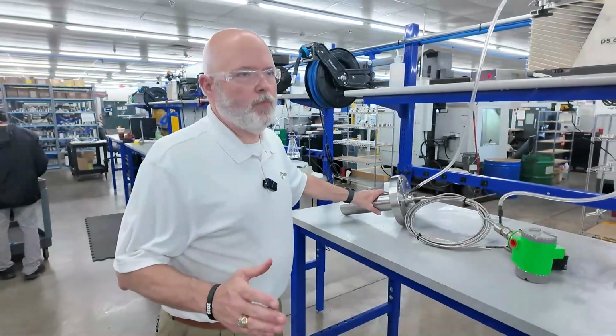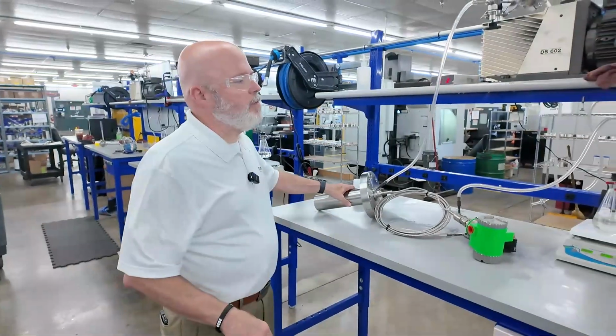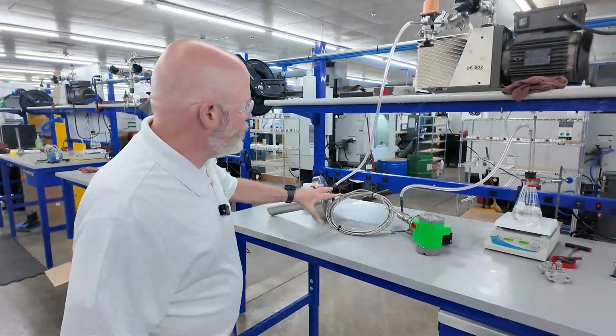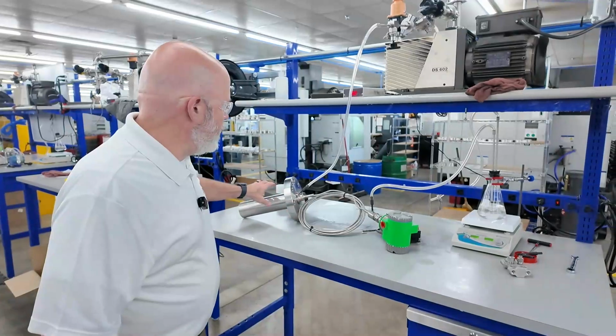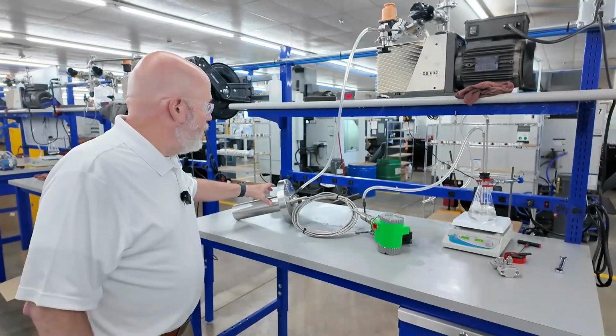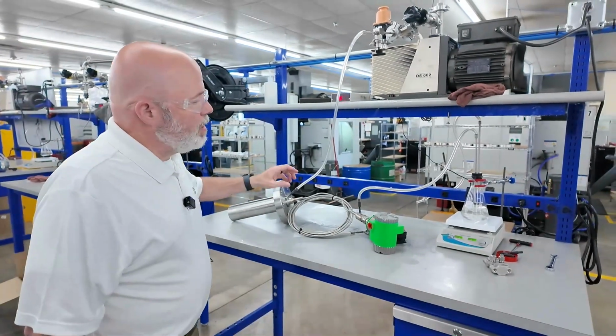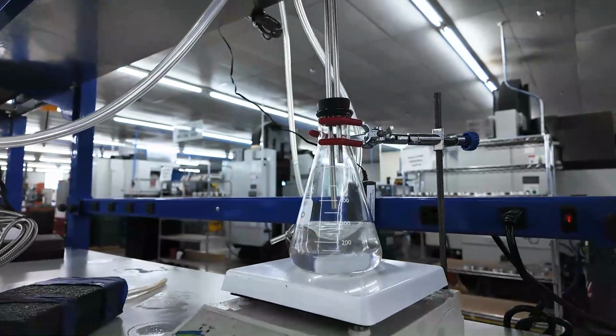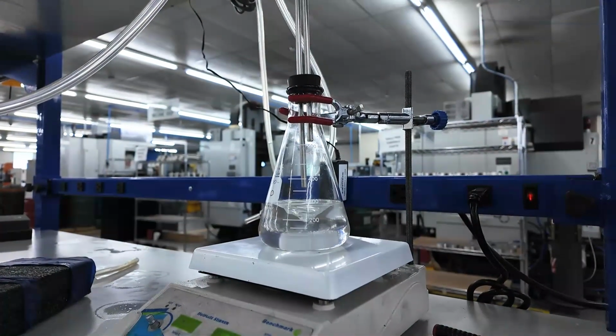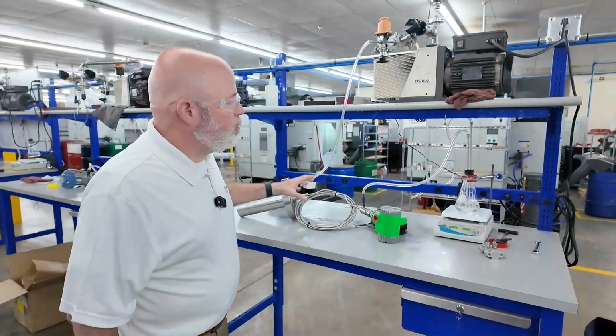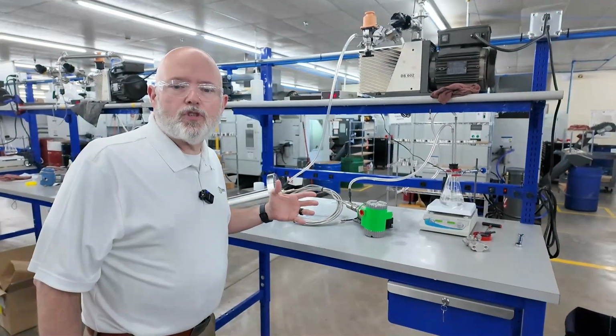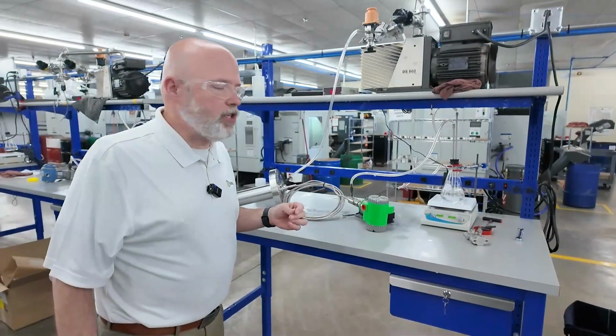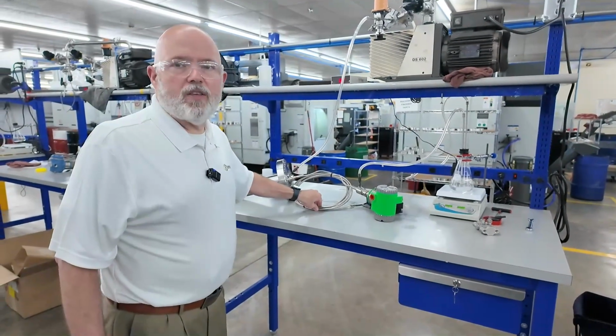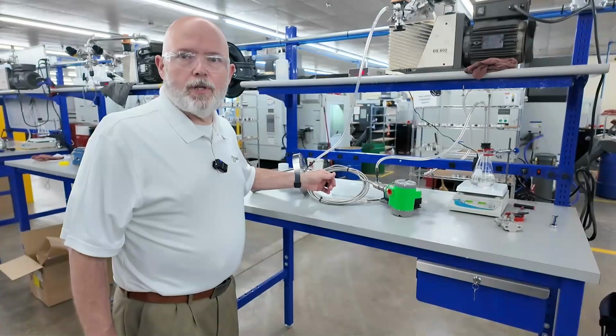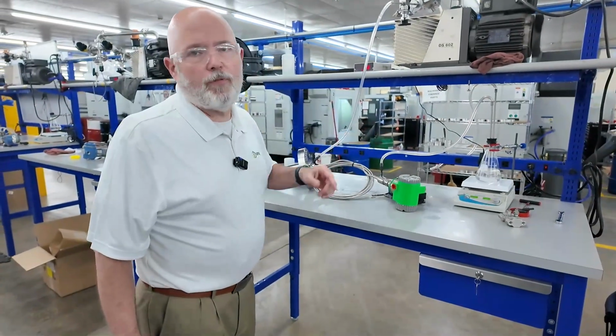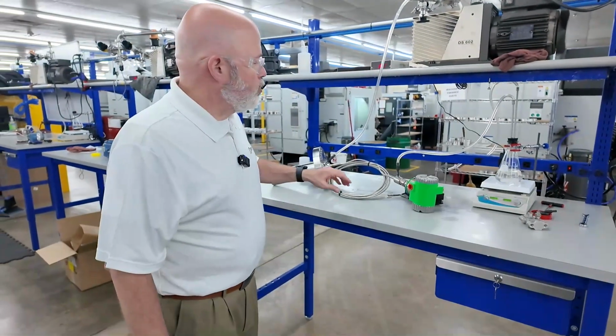It's a relatively simple process involving a vacuum pump, where we put the entire system under vacuum, including this extended seal. We also put the fill fluid under vacuum as well, to degas it. This stays under vacuum for a prescribed amount of time according to our procedure, depending on the length and diameter of the capillary, as well as the type of fill fluid being used.